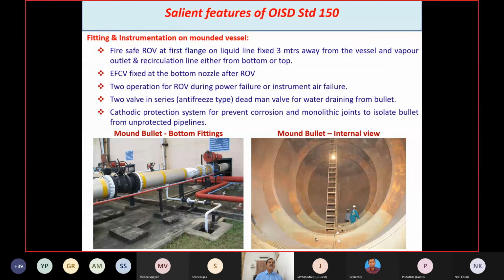So the bullet outlet, fire safe ROV at the first flange on the liquid line, fixed 3 meters away from the vessel, and vapor outlet and recirculation either from bottom or top. So the ROV will be at the first flange, fixed in the line. That 3 meter distance should be maintained, and the EFCV, external excess flow check valve, fixed at the bottom nozzle after ROV. After ROV, one excess flow check valve will be fixed.